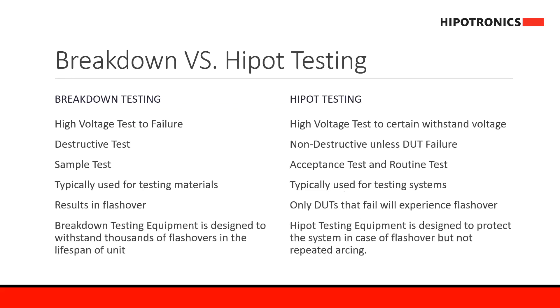Breakdown testing versus Hipot testing: for breakdown testing, the high-voltage test is done to failure. It's usually a destructive test, and therefore it's only done as a sample test. It's usually used for testing insulating materials, and the test will always result in a flash-over, since that's the goal of the test. With this in mind, the breakdown testing equipment is usually designed to withstand thousands of flash-overs in the lifespan of the unit.